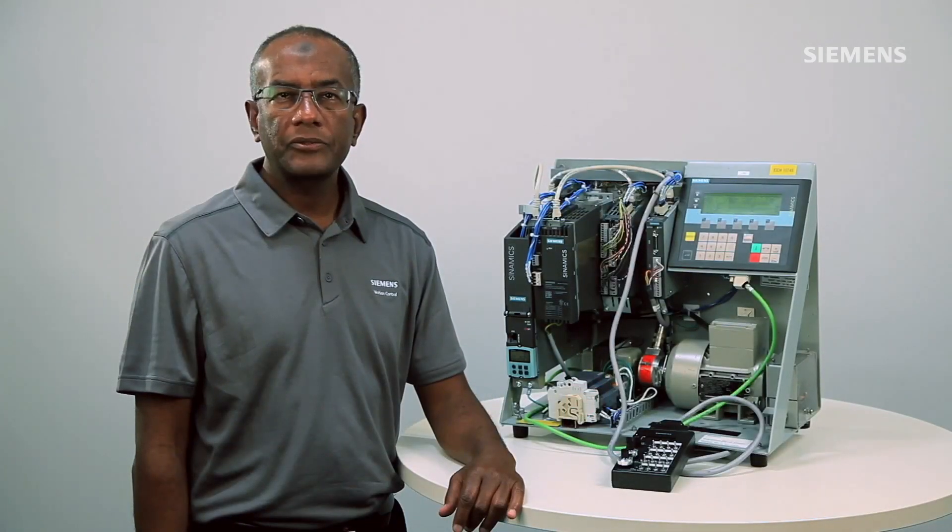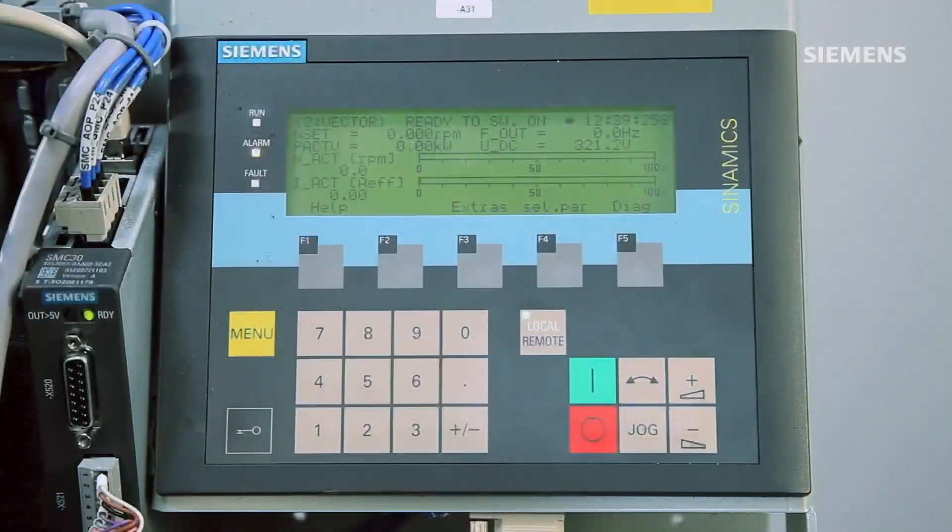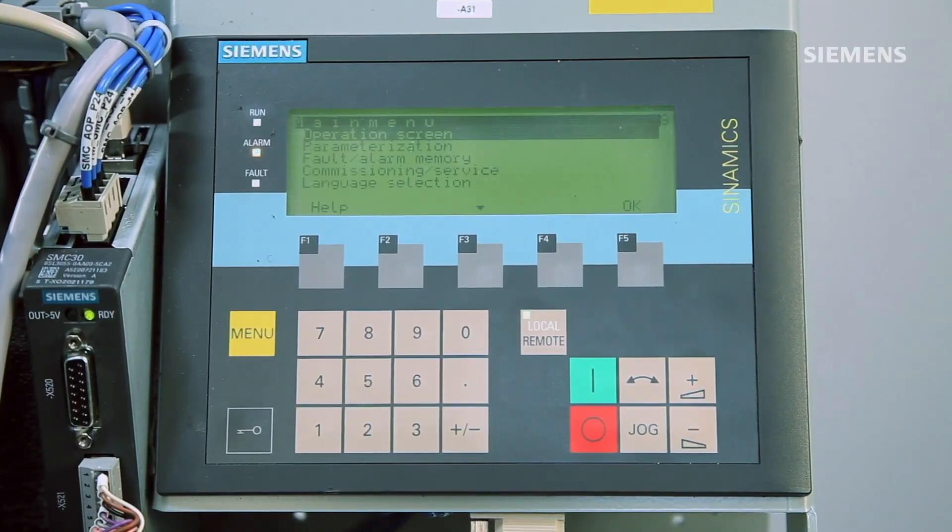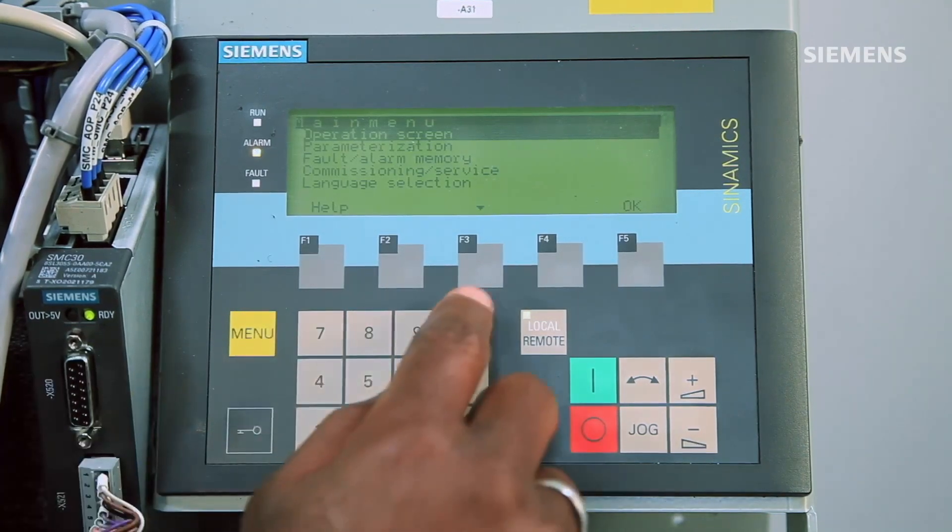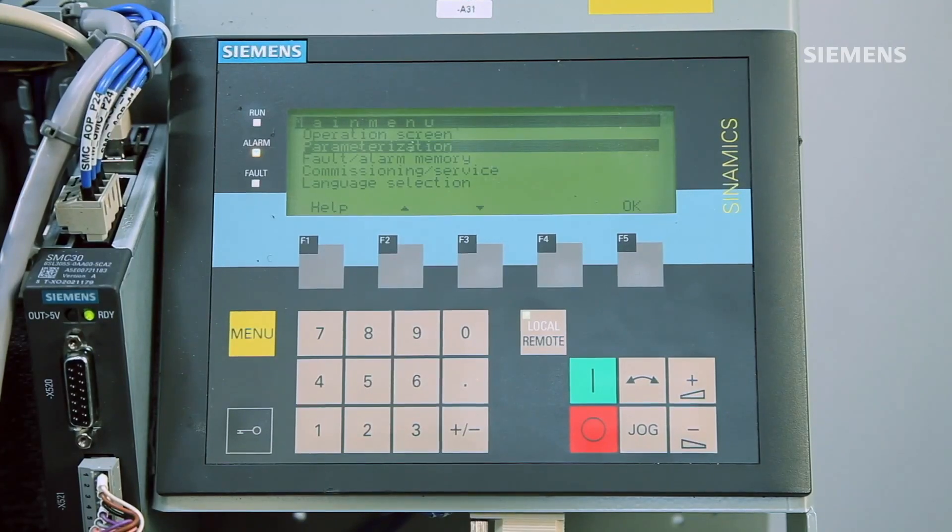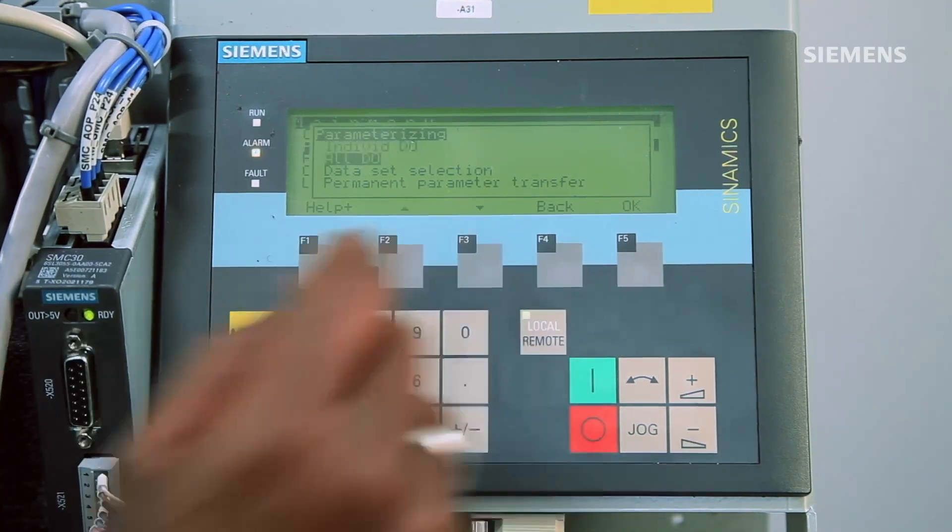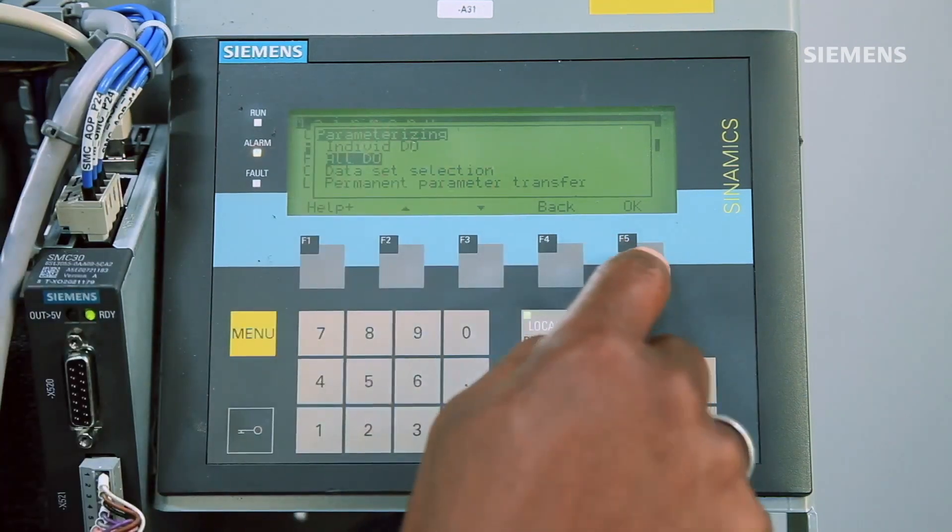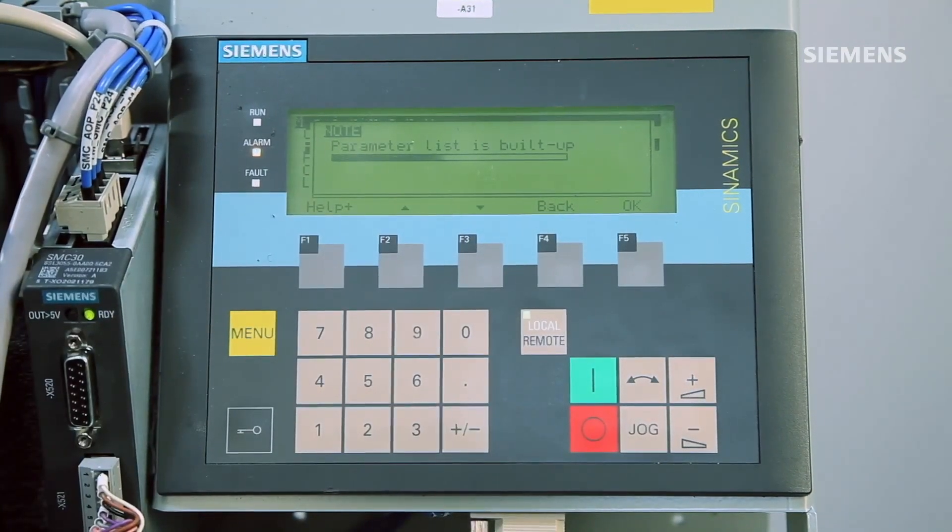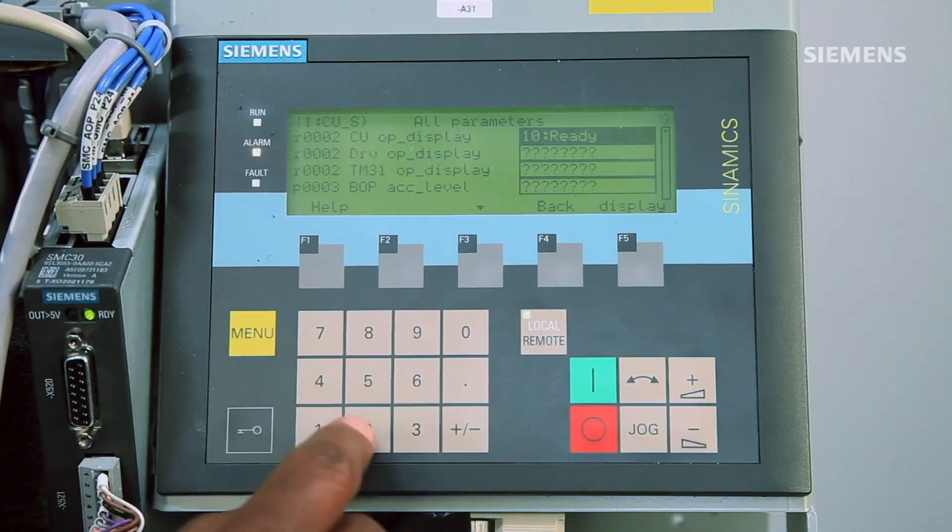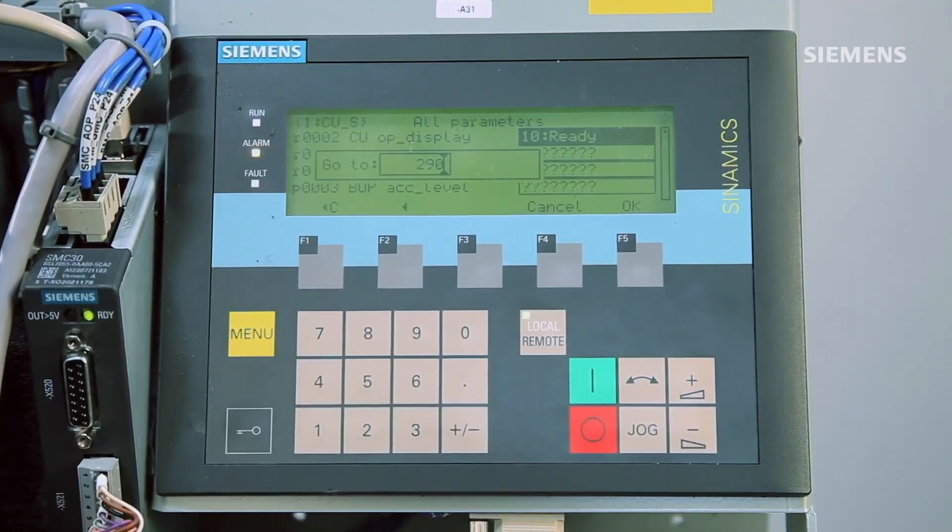To access the parameter to set up this overload avoidance, first select the yellow menu button to access the main menu. Using the arrow down key, select parameterization and then hit OK. Next we need to select all DO which means all drive objects and again hit OK. So now we have a list of all parameters from all the drive objects. Using the keypad, enter 290 and hit OK for parameter 290.